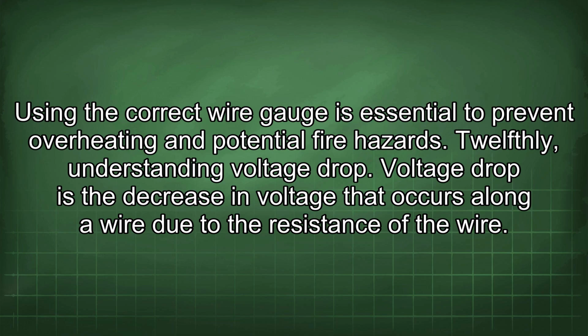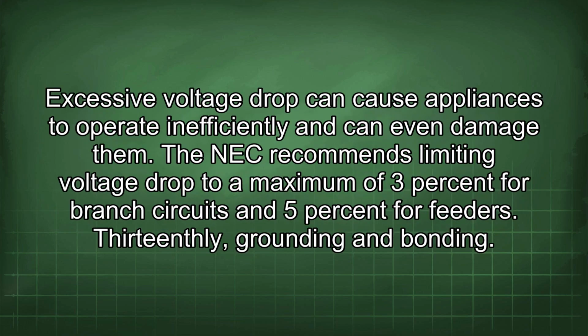Twelfthly, understanding voltage drop. Voltage drop is the decrease in voltage that occurs along a wire due to the resistance of the wire. Excessive voltage drop can cause appliances to operate inefficiently and can even damage them. The NEC recommends limiting voltage drop to a maximum of 3% for branch circuits and 5% for feeders.